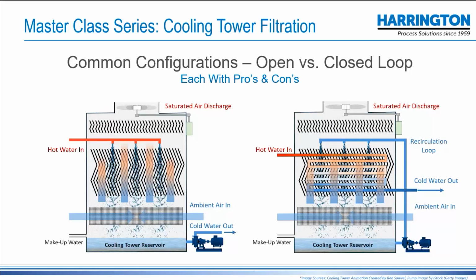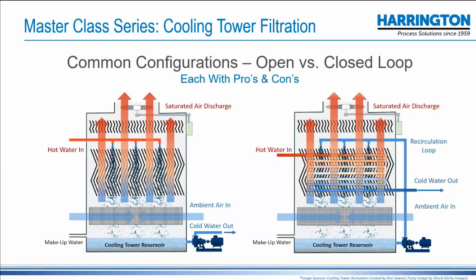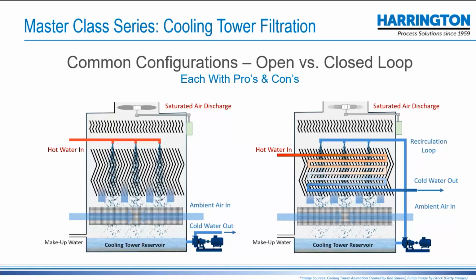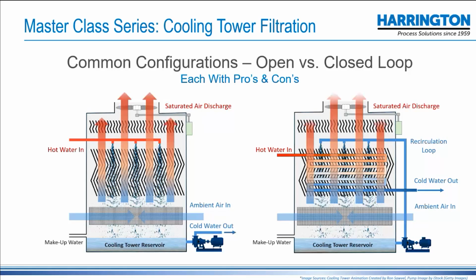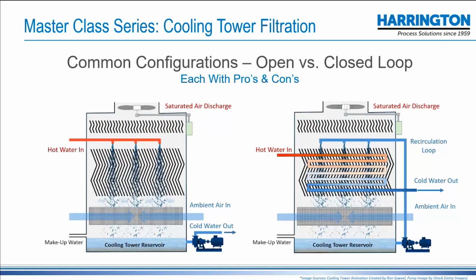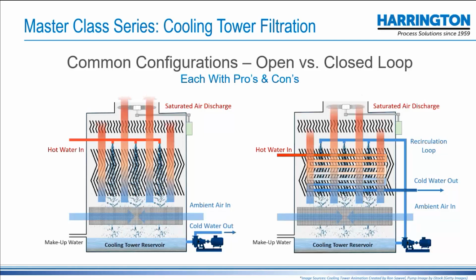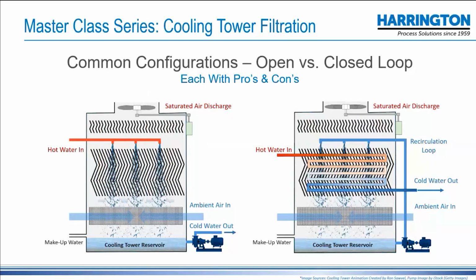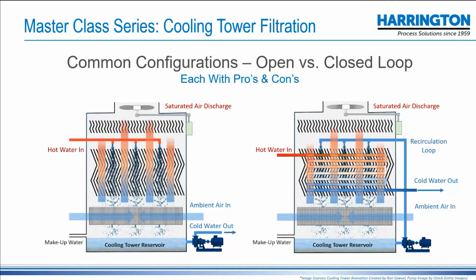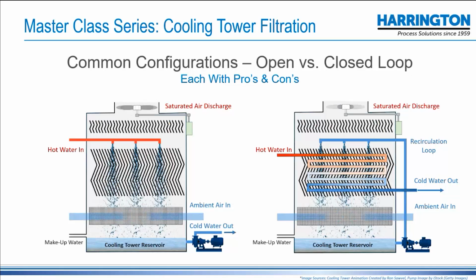Another thing is those dispersing elements, the cleaner they are, the more efficient they are. The nozzles that spray the water down on the dispersing elements can be clogged with debris. And so there's a very, very high level of need to keep that water clean. But by nature, it's drawing in all kinds of dirt, debris, organic material, bacterium, and other constituents that really helps if you can somehow clean that up.